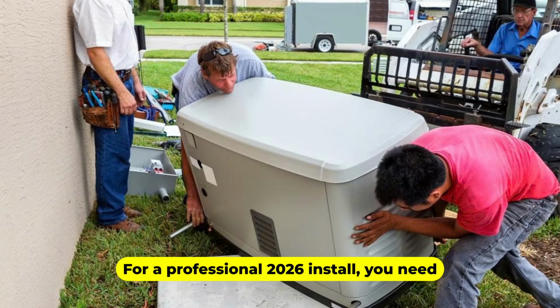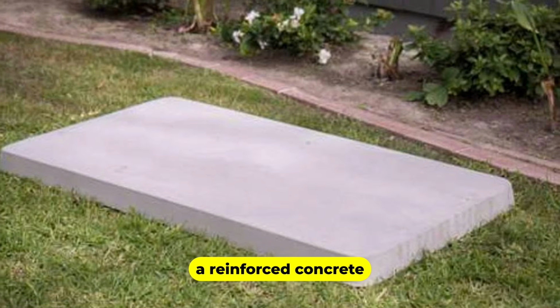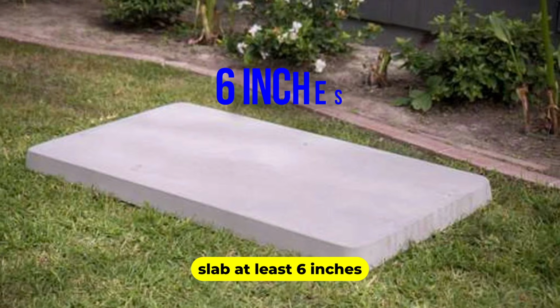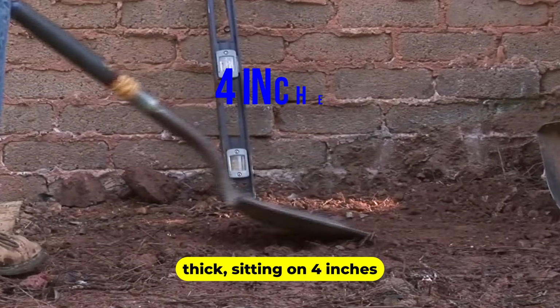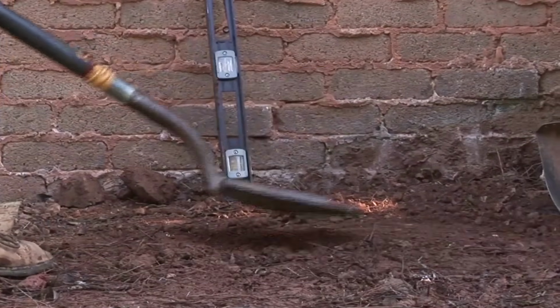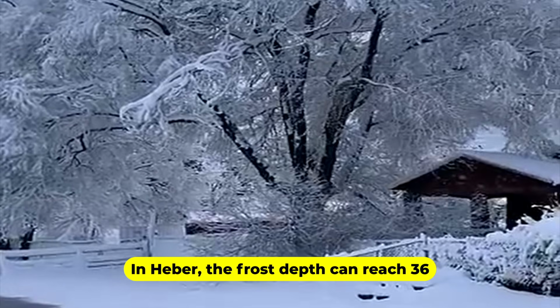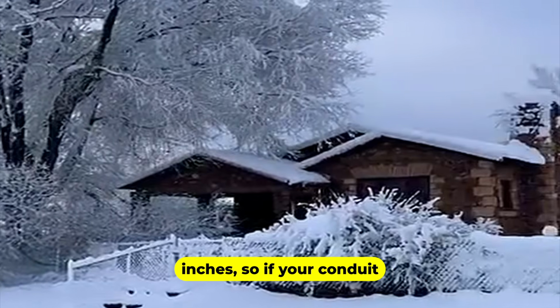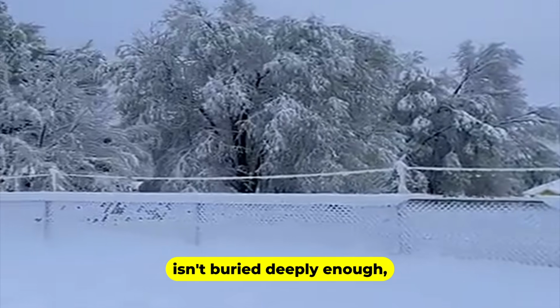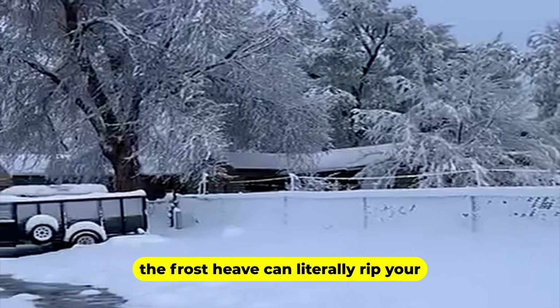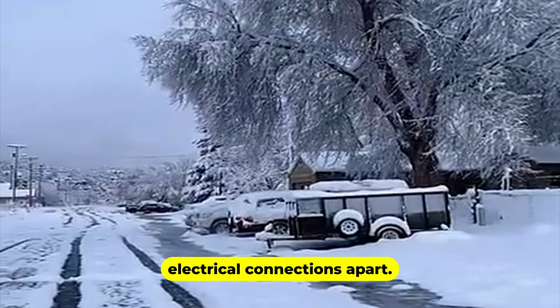For a professional 2026 install, you need a reinforced concrete slab at least 6 inches thick, sitting on 4 inches of compacted structural fill. In Heber, the frost depth can reach 36 inches, so if your conduit isn't buried deeply enough, the frost heave can literally rip your electrical connections apart.